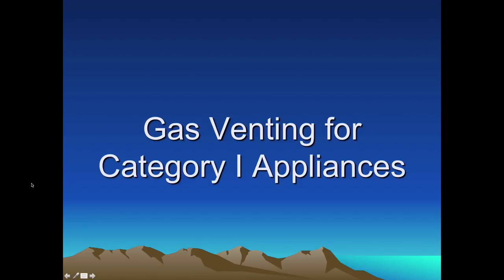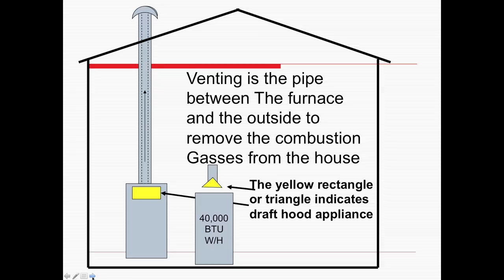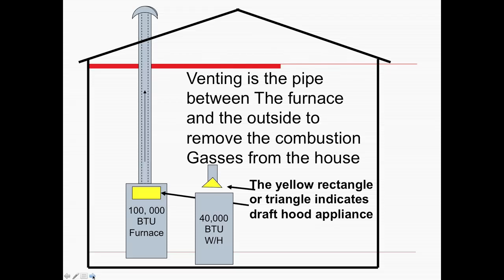This is gas venting for category one appliances. Venting is the piping between the inside and the exhaust on the outside of the structure. Here we're showing a draft hood. The vent temperature is above 140 degrees, it's vented with metal pipe, and the vent is under non-positive pressure. It could be a drafted appliance or a fan-assisted appliance, but the vent is still under non-positive pressure.